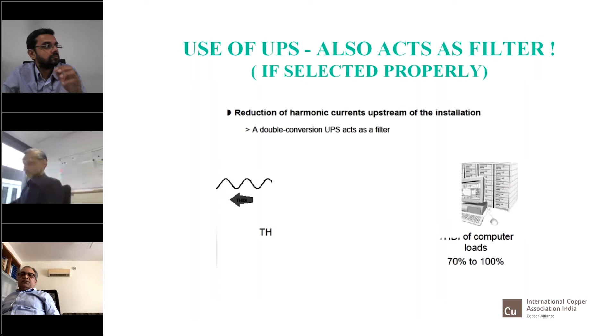UPS and how it protects. See, on the left side we have UPS, which could be specified as 3% THDI, or even 30%. If you don't specify, the fellow will give you a 30% THDI. Of course, I'm talking about third generation UPSs, which are nowadays not so much available. All UPS manufacturers have moved on to a better UPS.